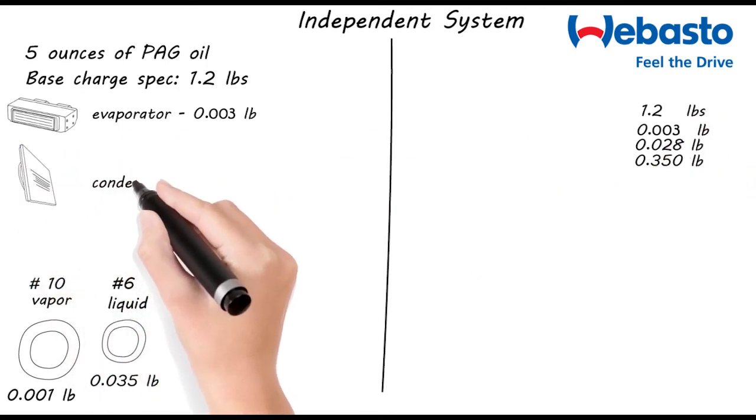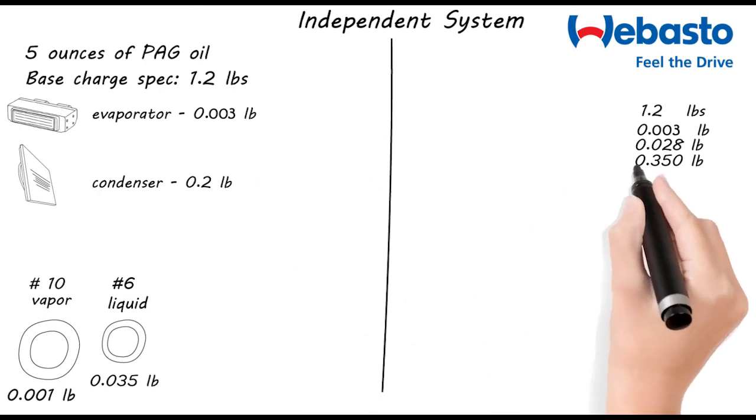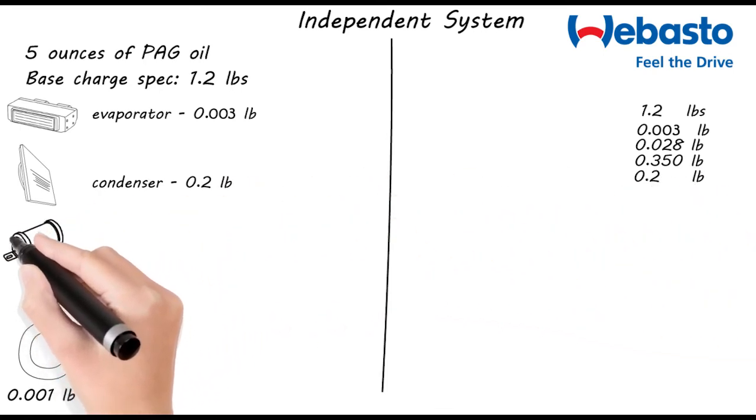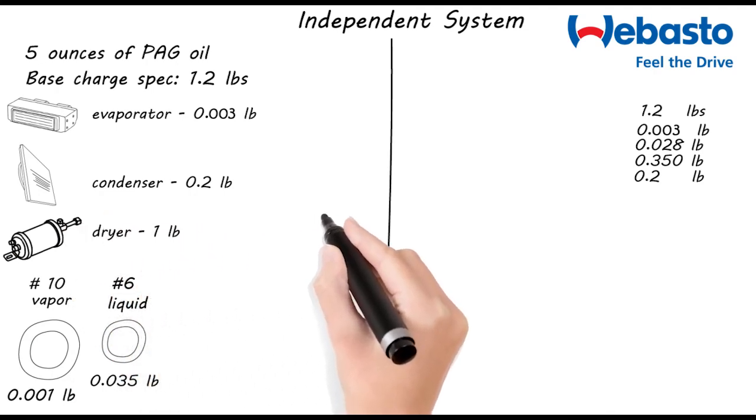The condenser holds a little less than a quarter of a pound, so we'll add 0.2 pounds. And we'll add 1 pound for the receiver dryer.